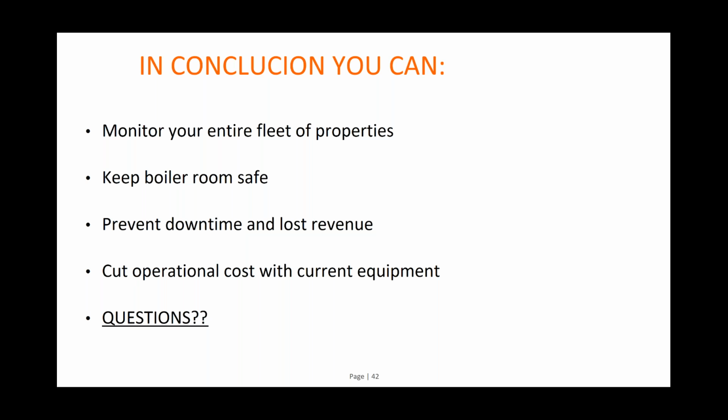Great question. We have started out with a very basic list. If you are in your mechanical room today, you think about all the stuff that typically breaks down without warning. Blowers, gas valves, electrodes, fouling, cavitation. So all the basic conditions that you see today, failure to ignite, for example, potential loss of supply. We are able to detect all the very basic conditions.